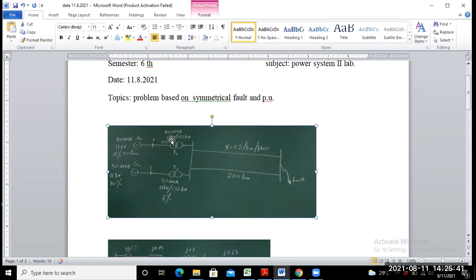That means MVA rating and voltage rating. This transformer is a step up transformer, which steps up the voltage, and power is transmitted through the transmission line. The transformer voltage rating is given as 11 kilovolt, 132 kilovolt, with 10% reactance. Similarly, for transformer 2, the MVA rating is 50 MVA and the voltage rating is the same as transformer 1, that means 11 kilovolt on the low voltage side and 132 kilovolt on the high voltage side. The reactance value is given as 8%.